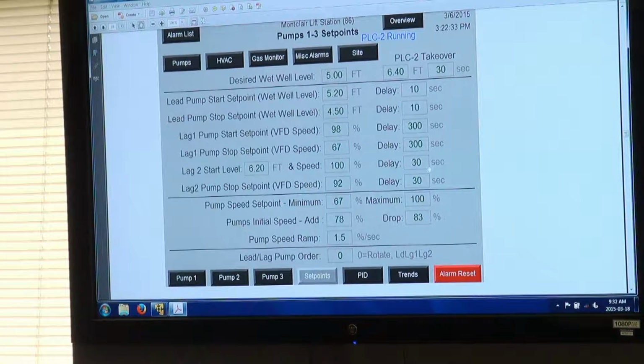I do have that delay at 30 seconds, not the 5 minutes, because we want to get that third pump started to prevent PLC 2 from taking over. Now pump 1 is going to stop, the third pump is going to stop at 92%, and then if you're running 2, it's going to go all the way down to 67.